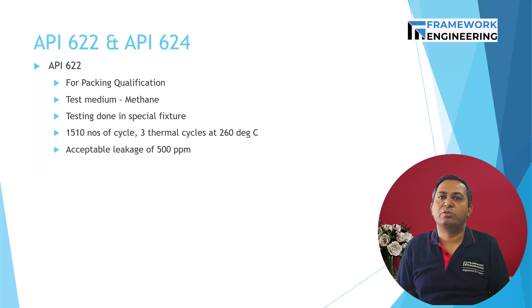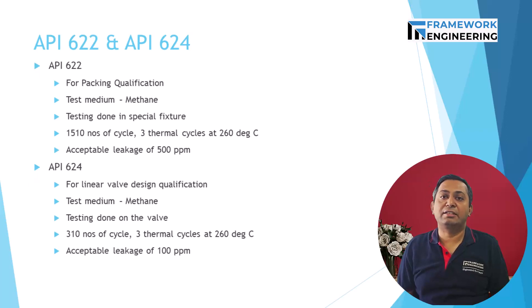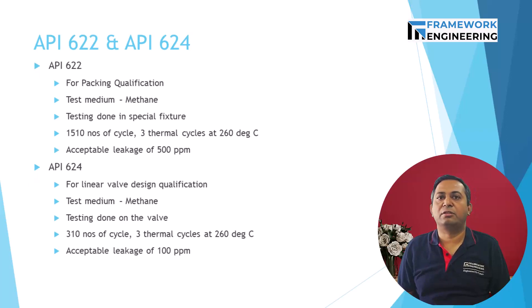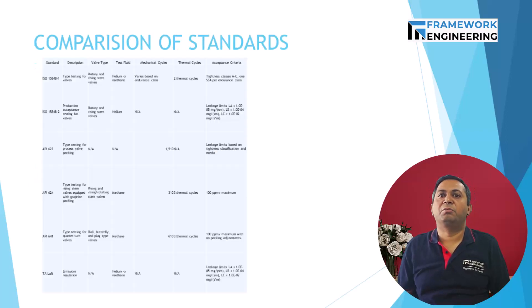API 624 is for linear valve design qualification only — rising stem valves equipped with graphite packing. It was developed in 2006 and published in 2014. The testing media is methane and testing is done on the valve itself — not on any fixture. The number of cycles is 310, with 3 thermal cycles at 260 degrees centigrade, and an acceptance criteria of 100 PPM only.